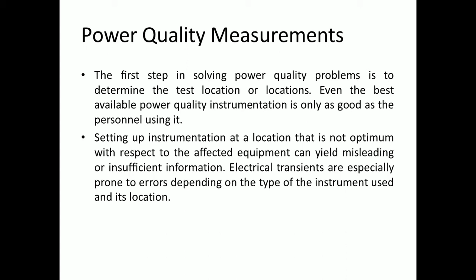So we'll continue further. Let's consider an example. That will make the point clear. Now, a large mainframe printing machine was shutting down. In a particular company, a large mainframe printing machine was shutting down randomly with no apparent cause clearly indicated. Now the machine was installed in a computer data center environment and was supplied with a UPS, that is uninterrupted power source, located about 10 feet from the machine. The power cord from the UPS to the printer was a 15 feet 3 conductor cable.